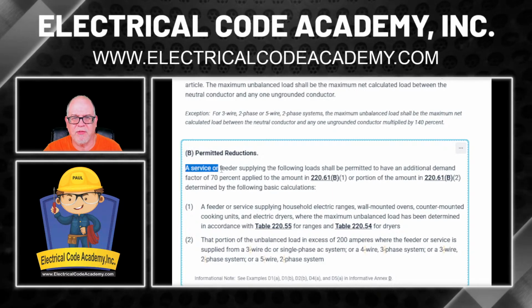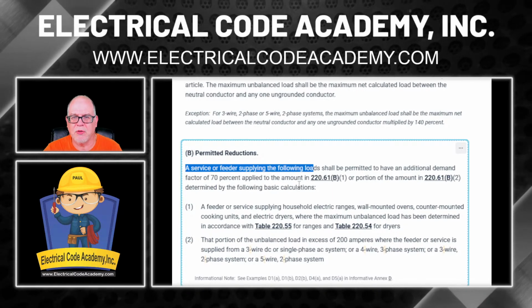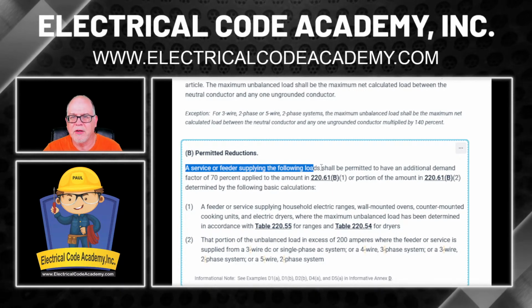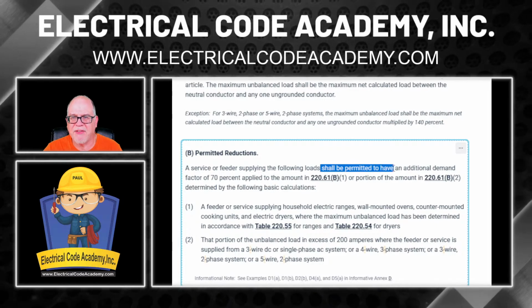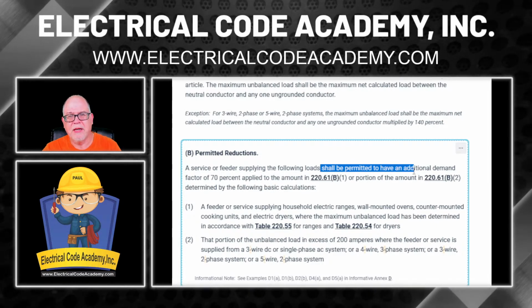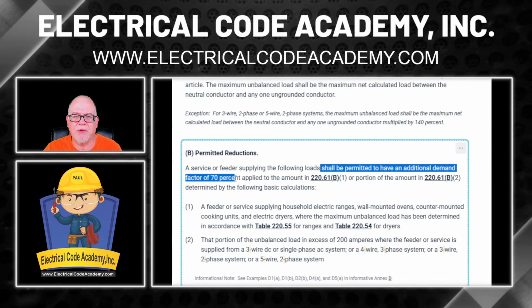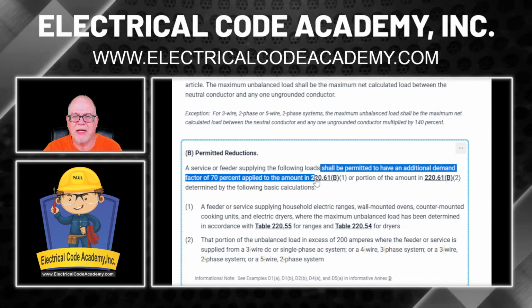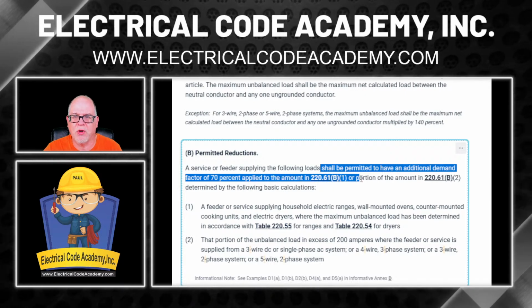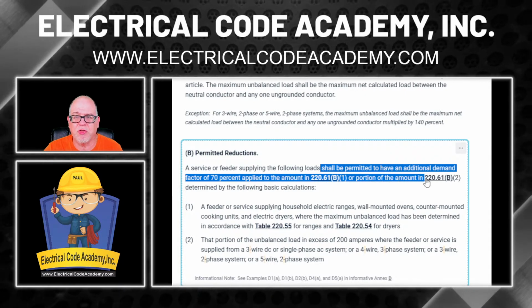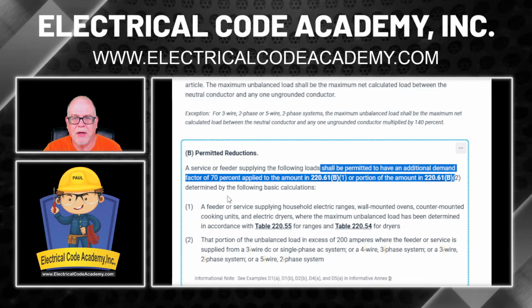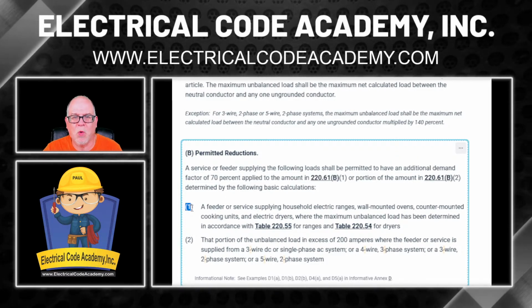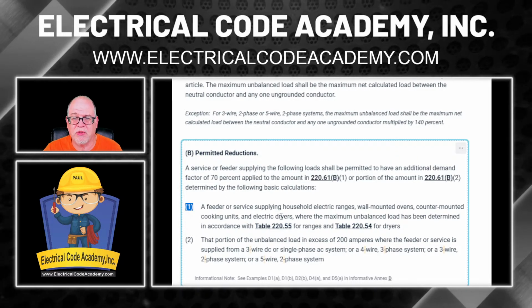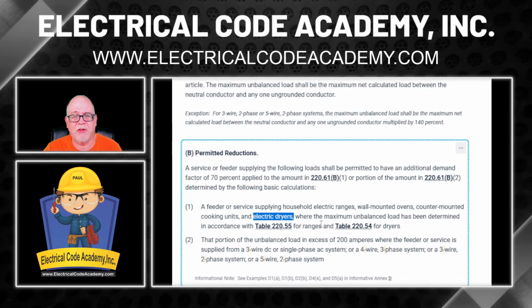It says a service or feeder supplying the following loads, that's these loads right here, shall be permitted to have an additional demand factor of 70% applied to the amount in 220.61(B)(1) or a portion of the amount in 220.61(B)(2). All right. Well, we're going to be doing B1 because, as you'll notice right here, electric dryers are in here.